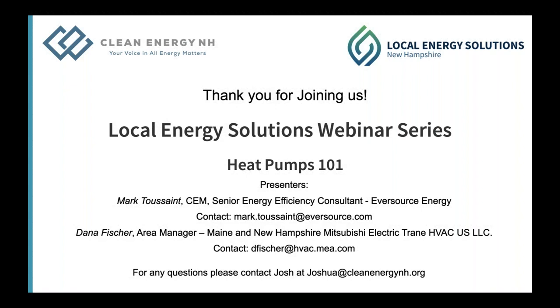And having a technician come out to your location and look over the entire system and make sure the indoor and outdoor units are all cleaned and operating within specifications. There's no real special magic tools to it. It's really not any different than having a technician come out and look at your conventional heating system. And so the costs are similar. It depends on the contractor and exactly what they're doing for the system, but it might be $100 to $300.